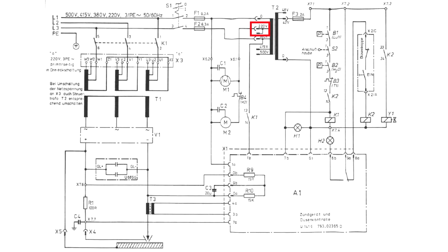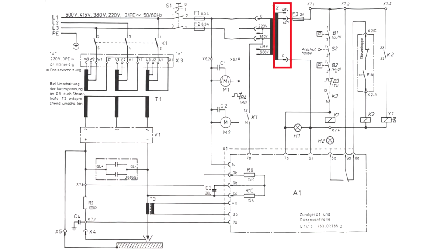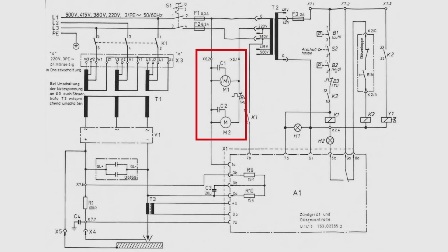The so far unknown load causing an overcurrent could be either connected to the secondary winding, which has its own fuse, or to something connecting to this primary tap. And two things which connect to that tap are the big fan and the pump of the cooling system, so that is where we have to look next.